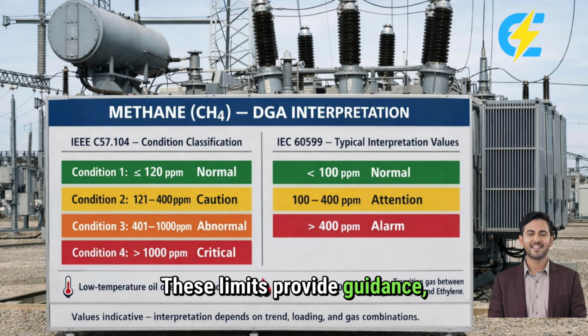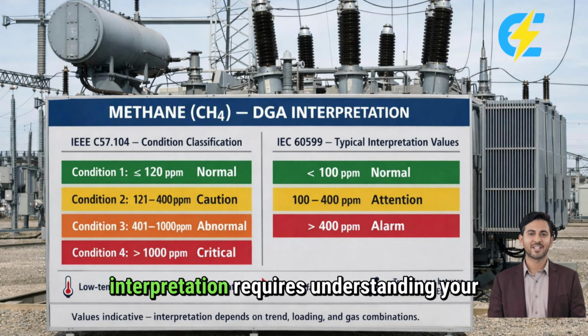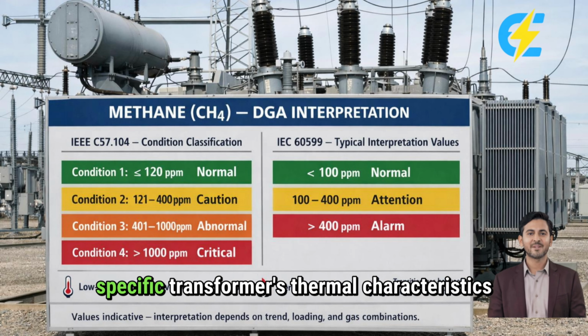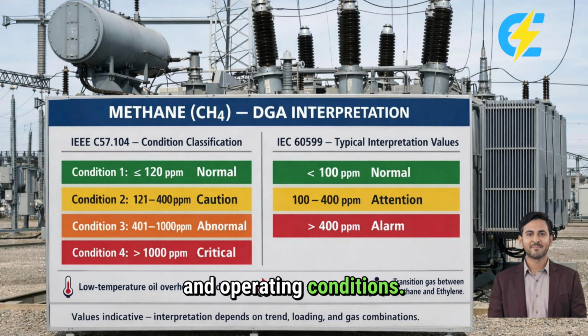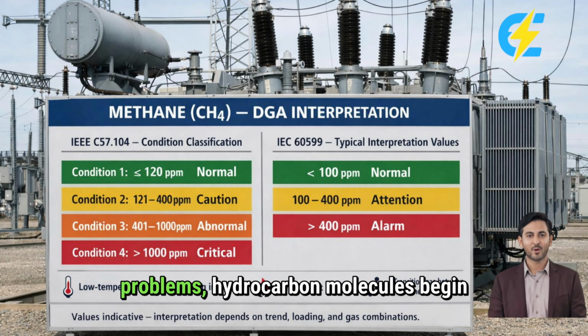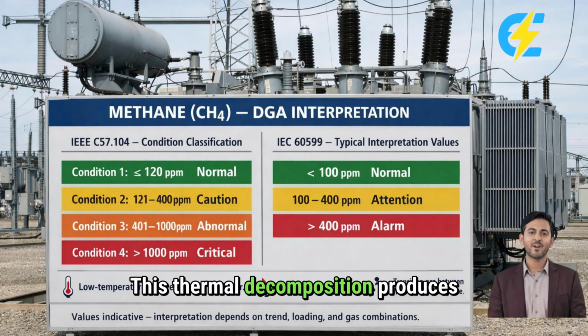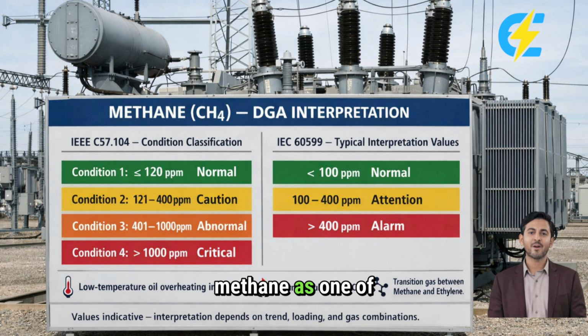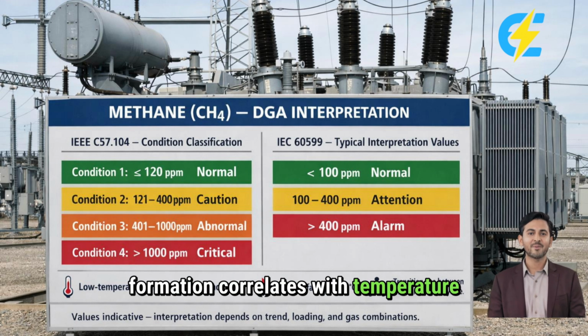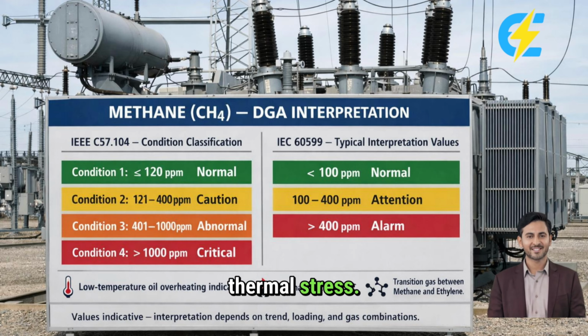These limits provide guidance, but remember that methane interpretation requires understanding your specific transformer's thermal characteristics and operating conditions. Methane formation links directly to thermal stress mechanisms. When oil temperature rises due to hotspots, overloading or cooling system problems, hydrocarbon molecules begin breaking down. This thermal decomposition produces methane as one of the primary gases. The rate of methane formation correlates with temperature levels and duration of thermal stress.